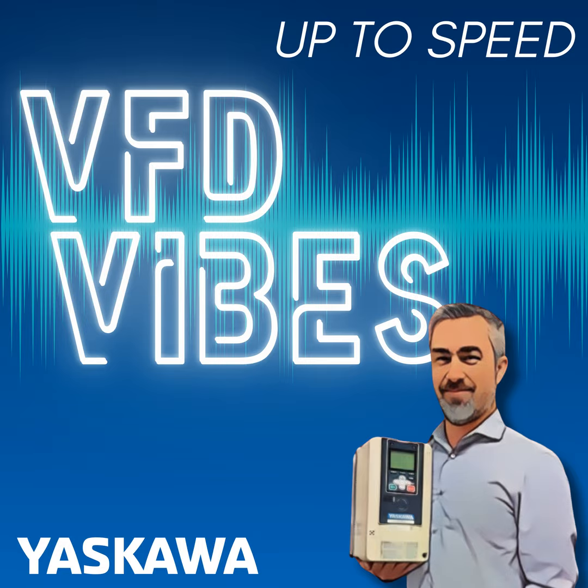Now, on that same aspect, let's say he had a 1 digit all the way to the right. We confirmed a run command. Okay. And you said you're sending 10 volts on A1. Yep. And there's nothing there. Okay, let's look at U1-13. Now, there's 2 analog inputs on the HV600 drive, and many of the other drives, even in the industrial, may have 3 inputs. But there are monitors U1-13 and 14, which look at A1 and A2. So if he was sending 10 volts on A1, we'd look at U1-13, which shows the raw input value that A1 is seeing. And in this case, he's going to tell me it's 0.